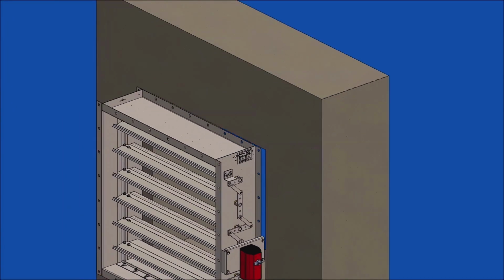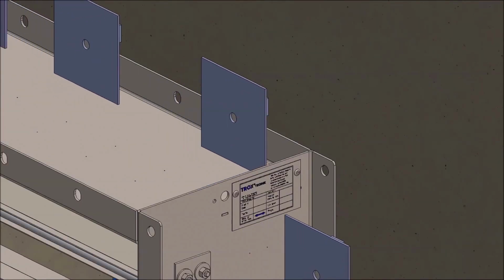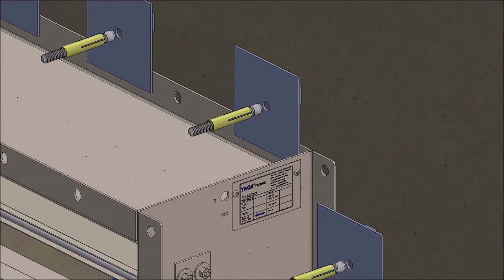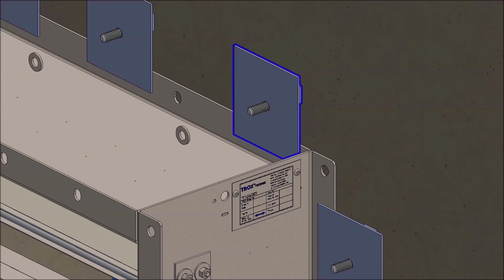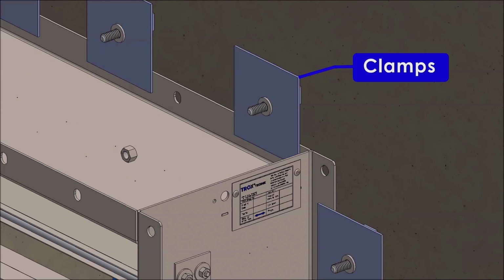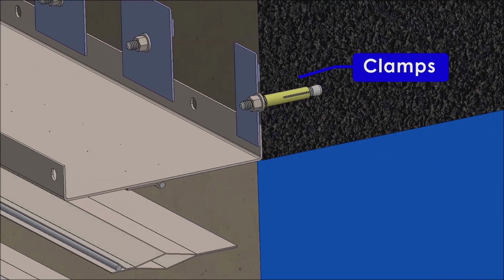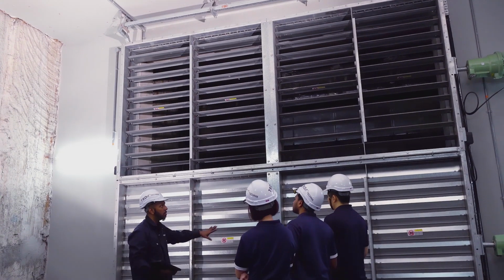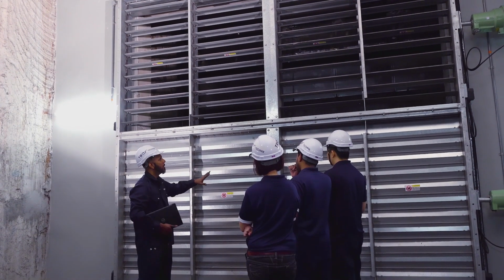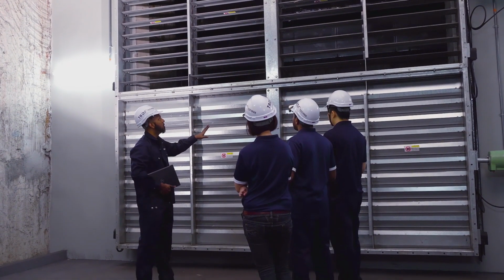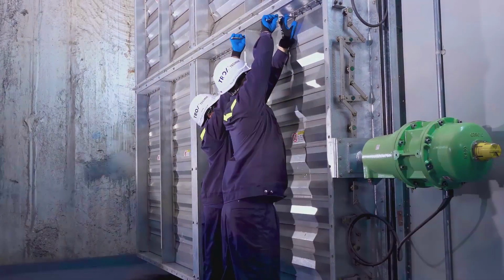The dampers are suitable for direct mounting to concrete or to steel ductwork using the punched flanges provided. For installation on concrete, clamp plates can be provided to simplify the installation process and ensure that the minimum edge distance for the installation of anchor bolts can be maintained. TROX project engineers provide site support in the form of training, both prior to installation and commissioning.